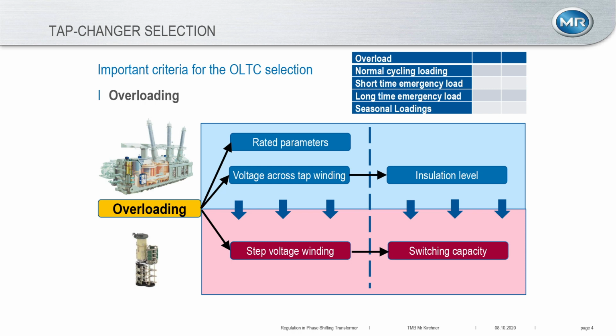But what is special about this application is, if we increase the load on a phase-shifting transformer, the step voltage will increase as well. And this is very unique, because if you look at a normal power transformer and increase the load, the step voltage is going to stay constant. But this is different here. So if the step voltage increases with the load, the switching capacity of your on-load tap changer is affected. And this is something you have to consider, and this will lead to certain limits.